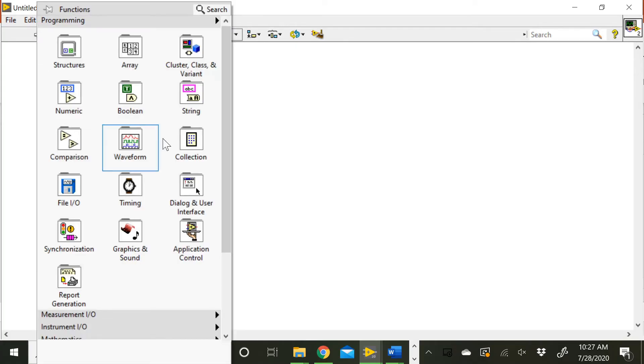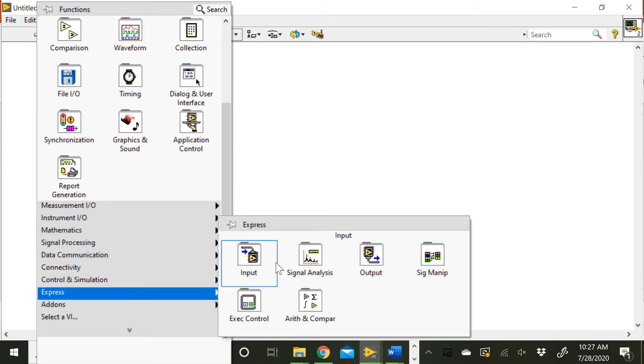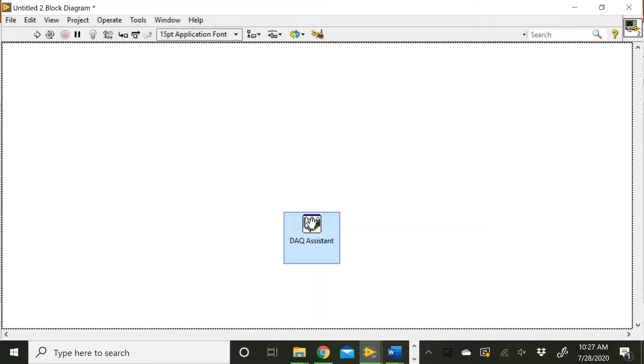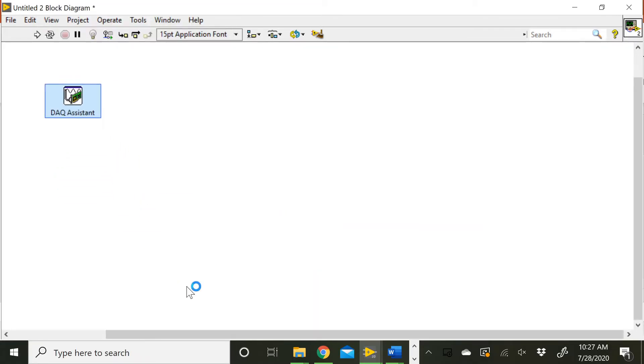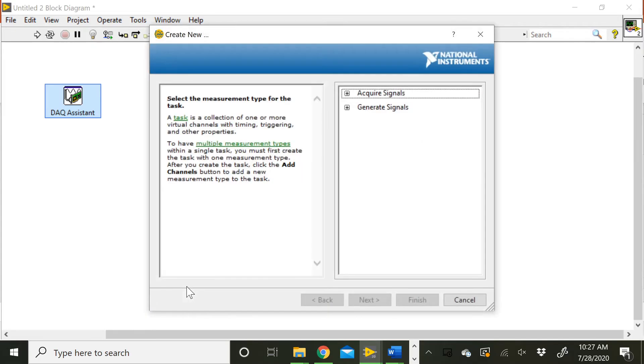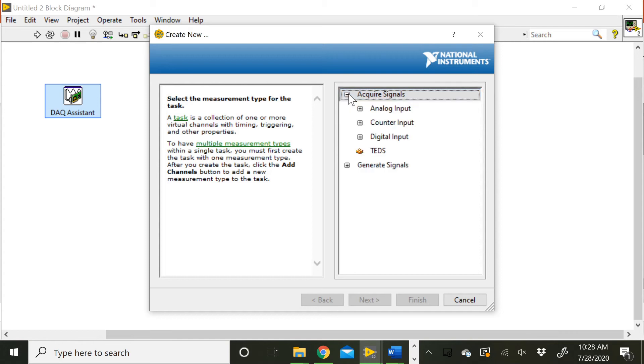Go ahead and right click and you should be able to scroll down to express, then input, and you'll find the DAQ Assistant here. So the DAQ Assistant is an express VI, which means that it pops up with one of these menus where you configure it. When you drop it down, it's going to go through this initializing step. It's going to ask us what we want to do. We could set this up to generate an output through our analog outputs or the digital outputs on the DAQ. That's not what we're doing today. We're here to acquire a signal. So you drop that menu down to acquire a signal. We are acquiring an analog input. Remember, the thermocouple is producing a voltage signal. So what we're ultimately doing is we're reading that voltage into the DAQ, and then we're going to convert that into a temperature using math.